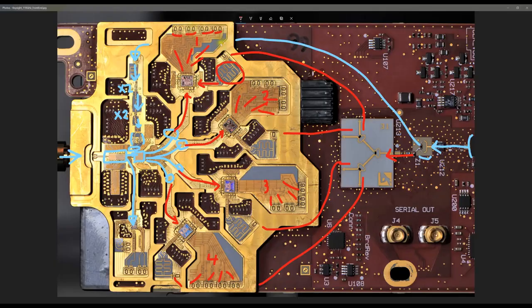Now if you look closely again, the ADC inputs from each other are fully isolated, and this reason is because it is a little bit easier to handle crosstalk within each ADC than between the ADCs. So the isolation between the lanes of these ones coming out is very important. I also want you to appreciate how difficult it must be to isolate the clock from leaking into the A to D converters, because you have 16 gigahertz clocks everywhere in multiple phases. You have multipliers and doublers which create harmonics and intermodulation products. All of these things coexist in this front-end module, all of which have to be filtered properly in order to make sure that they don't feed into the A to D converters.